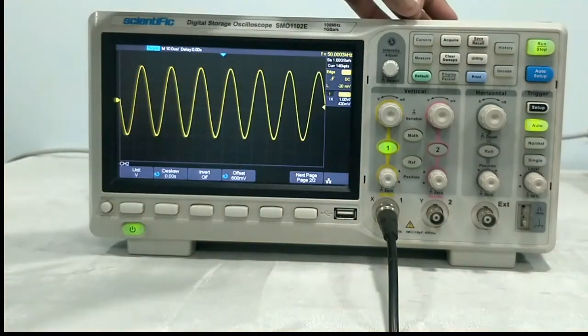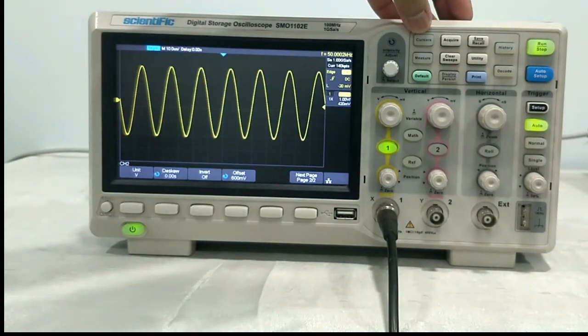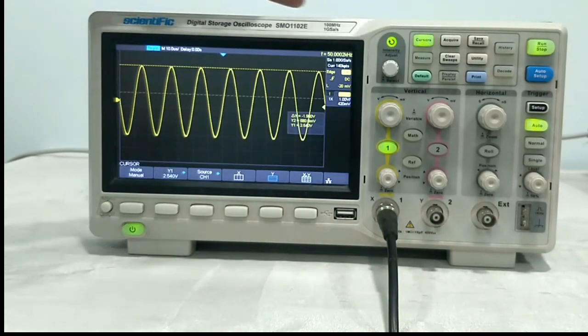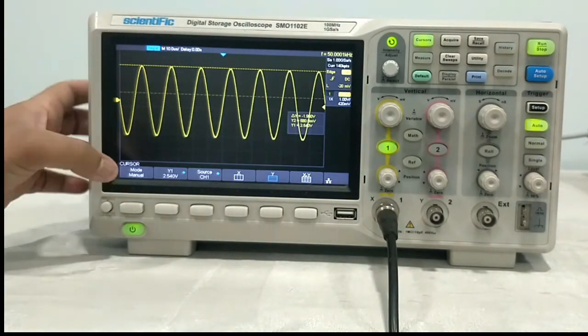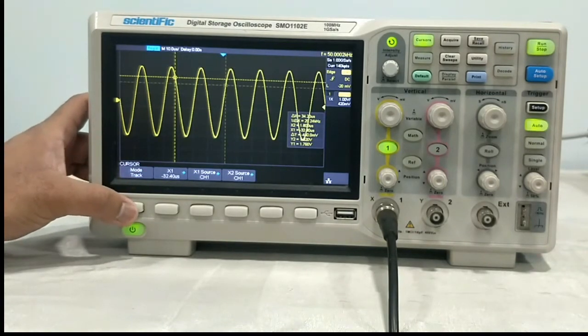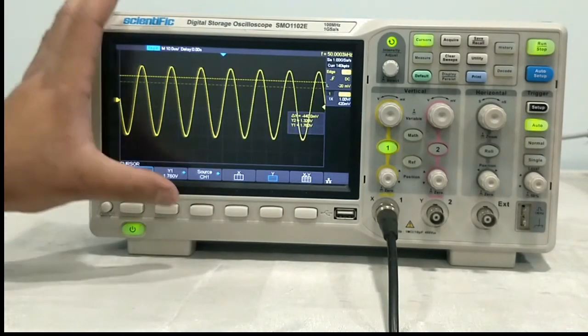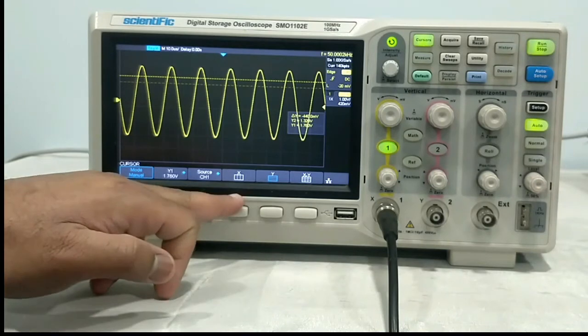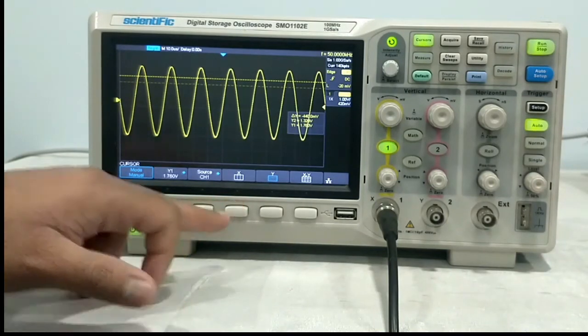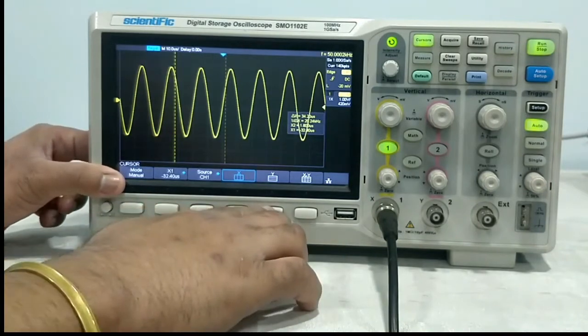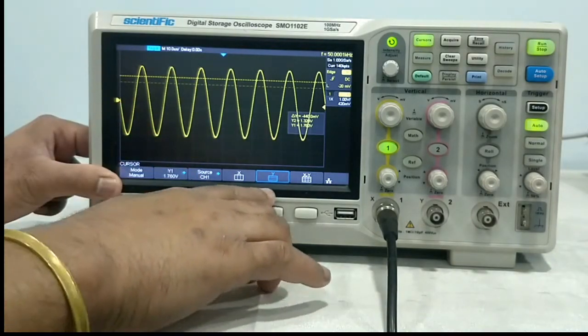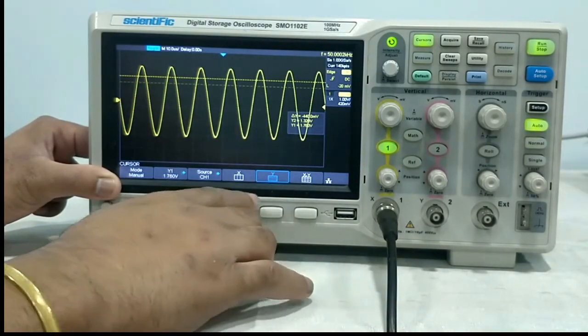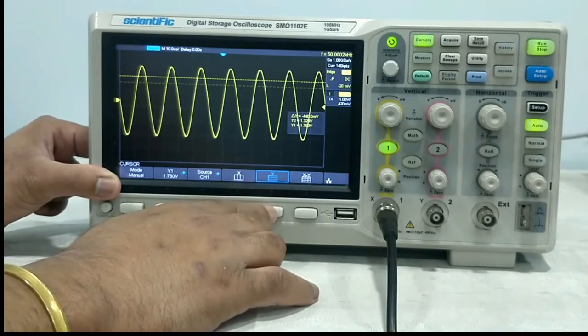Now we will come to the functions. First one is cursor. If you go to cursor, you can set the cursor and measure the signal. Right now this is in horizontal. First comes the mode — you can have manual or track mode. We will put it to manual. Source, you can select from here. If you want X cursor, those are the vertical lines — you have to select this. If you want horizontal cursor, that is Y. If we want to measure the amplitude of the signal, we will select Y cursor. You can have both X and Y also.